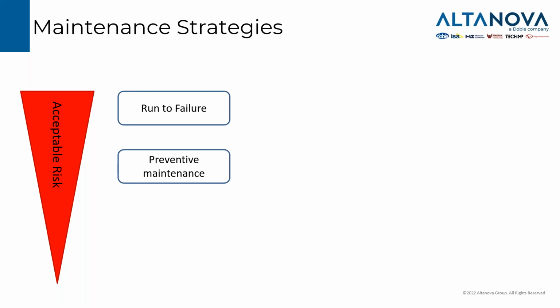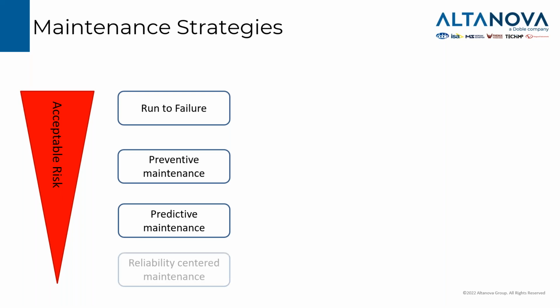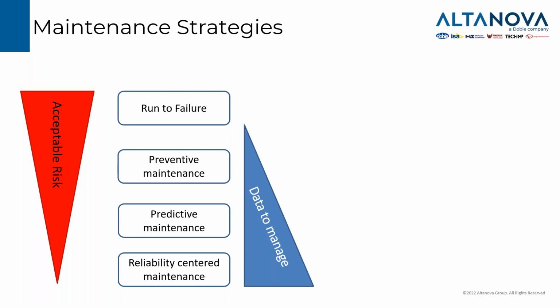From this stage, when we want to reduce the acceptable risk, we can work on preventive maintenance. So we have a time-based maintenance plan or testing plan for the asset. Then we can have a predictive maintenance approach that reduces the risk again. So we try to get more information about the asset. We manage this data in order to reduce the risk of failure. And the lowest acceptable risk that we will find is when we have maintenance that is based on the reliability of the asset. Of course, we will have increasing data and information to manage when we move from run to failure up to predictive maintenance, and we can have different steps of information that we manage.